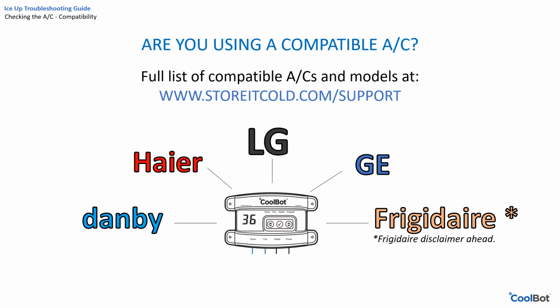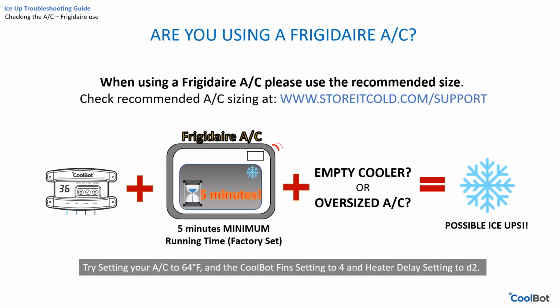Are you using a compatible air conditioner brand with your CoolBot? For a list of supported brands and models, visit our support page at www.storeitcold.com. Note that if you're using a Frigidaire air conditioner that is oversized or that is installed on an empty cooler or during the winter, you may experience freeze-ups or colder temperatures than the set point. The Frigidaire air conditioner has a minimum runtime of 5 minutes, so in a well-insulated cooler, the cooler may go below its set temperature and can cause freeze-up problems. Because of this, we encourage you to use the recommended size air conditioner to reduce the chances of icing up.